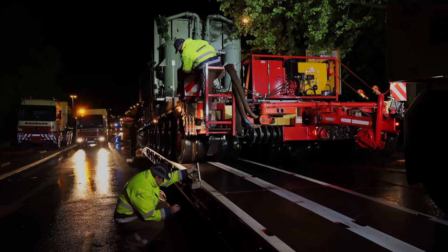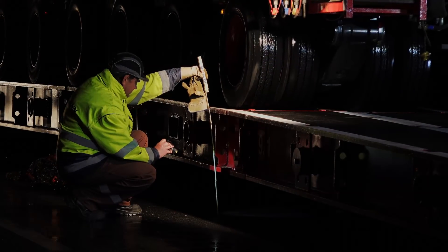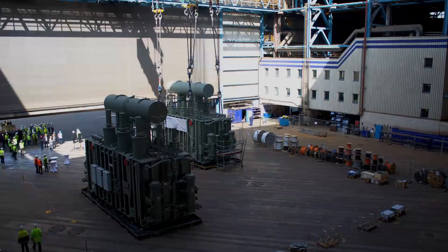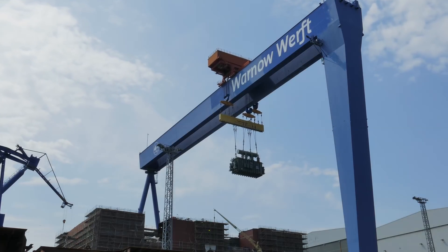Transporting the transformers was a Herculean task. Bridges needed special reinforcement, the load had to be checked constantly for proper hydraulic weight distribution, and high-voltage railway power lines had to be lifted. Now and then, a few minor modifications were necessary — rarely carried out by German drivers in a rush. In Warnemünde, the two offshore transformers — each now filled with 100 tons of oil and tested in spill basins — are lifted into the topside.